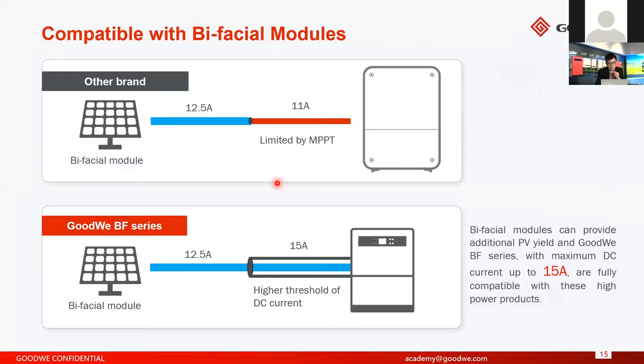And for all our C&I products like the MT series and the HT series, we are compatible with bifacial modules. For example, for our BF version, just now I already mentioned the BF version of the MT series. On the DC side, maximum we can support 15 amps on each string. So that means, for example, in the market now, normally the bifacial modules' output current is around 11 amps, maximum up to 12.5 amps, but the inverter can accept 15 amps. So our inverter is compatible with the bifacial modules, and you can get more generation on the DC side.